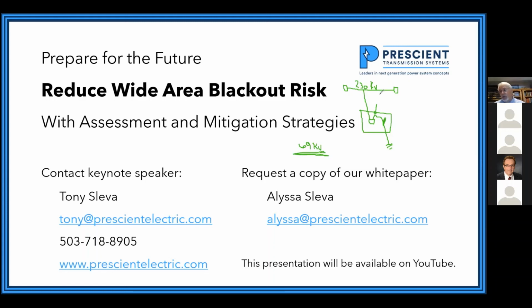So this could be faults on the 500 kV system or the 345 kV system or the 230 kV system. And the load testing would be at a lower voltage, 138 or 69 kV, with less risk to the power grid. You could also use that data to calibrate your transmission steady state and dynamic models as well. Yes, yes, yes. So there's a lot of really good things we could do, and there's a lot of good products out there we could be using, and somehow we have to get enthusiastic and start putting all these things in play. One last question for me.